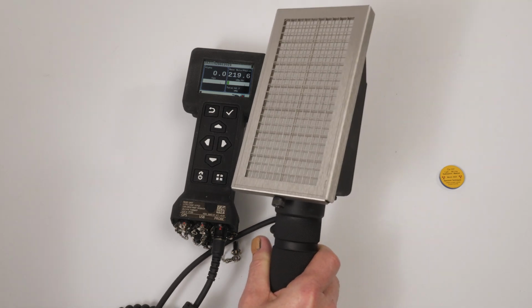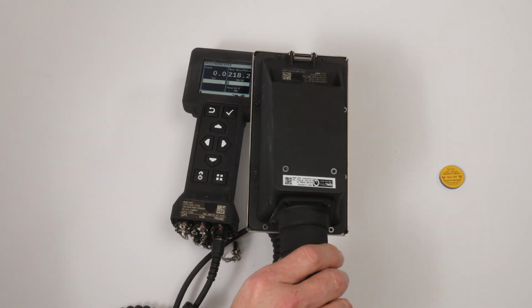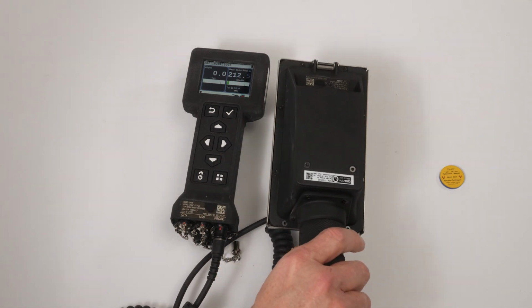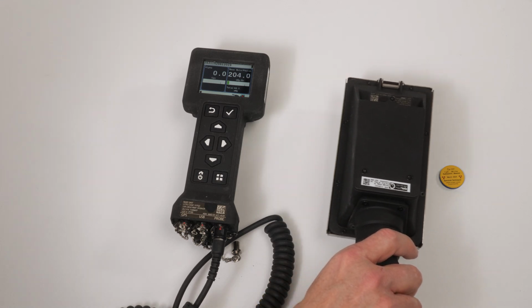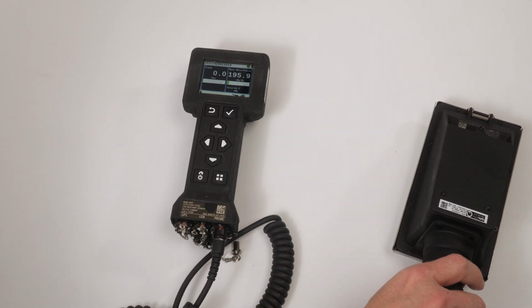The alpha-beta probe is used to monitor for alpha and beta radiation. Both alpha and beta radiation have a very short range in air. Alpha and beta radiation monitoring must be performed with the front face of the probe in close proximity to the area being monitored for contamination. To operate the probe, hold the alpha-beta probe by the handle. Hold the probe close to the suspected contaminated surface by moving the probe at a pace determined by your standard operating procedures.